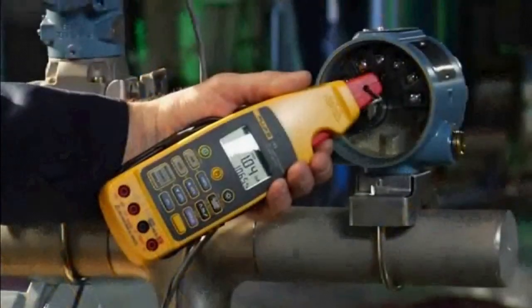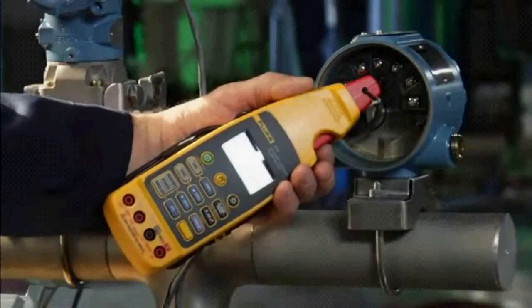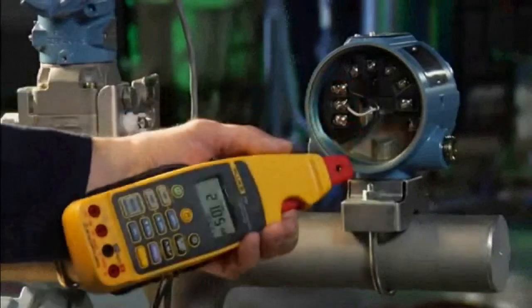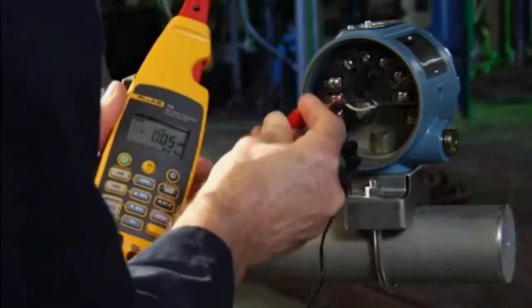Next, substitute test the transmitter with the Fluke 773. Remove the signal wires from the transmitter and break the loop. Connect the test leads from the Fluke 773 to the transmitter wires to use the milliamp simulate function.